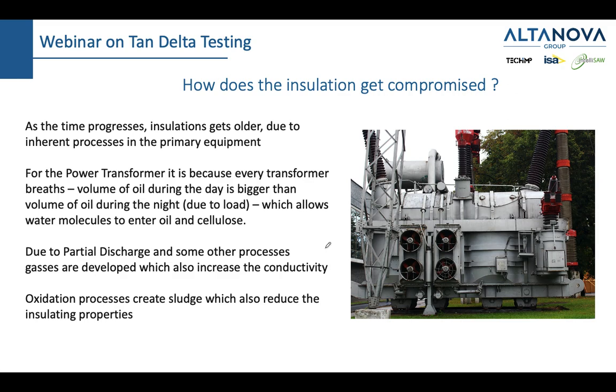At the beginning of that pipe, you have some silica gel, which is put there for a reason, which is to remove all the water molecules from the air. And it does a good job. You know that you need to change that breather when it changes color, sometimes from blue to white, sometimes there are some other colors. But the point is that even though you have the breather, it is not perfect. Like an ideal transformer, it doesn't exist. There will always be some water molecules which enter the transformer. And these water molecules contribute to the conductivity of the insulator, of the oil. And also these water molecules usually stay in the cellulose. I would say 90 to 99% of all the water which is in your transformer is actually in the cellulose, in the paper and the press board. It is not in the oil. Another reason how our insulation gets compromised is, let's say, partial discharge.